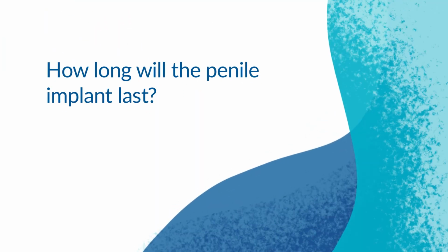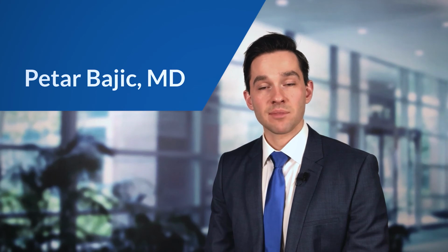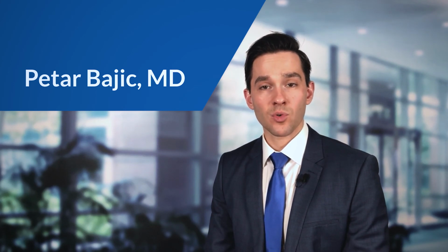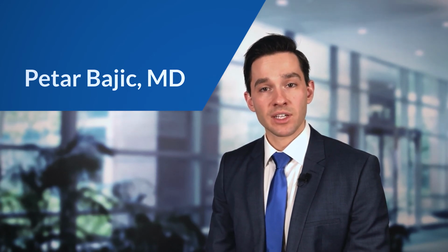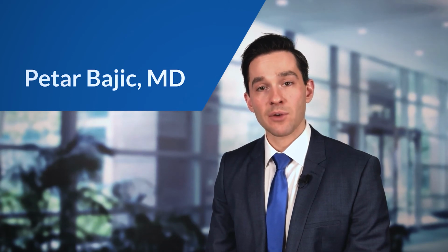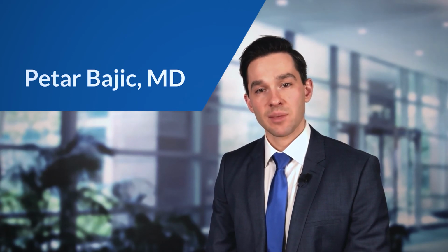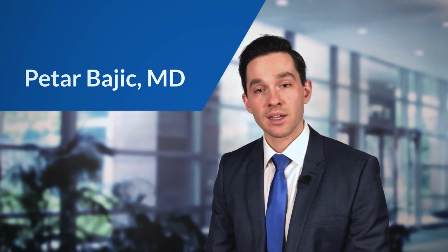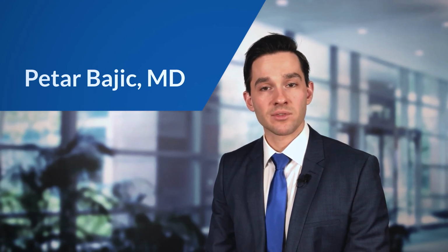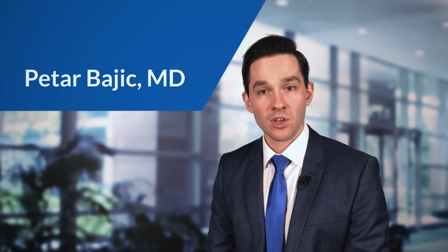As far as how long the penile implant lasts, I've seen many men who've had the device for over 30 years and still use it regularly. However, in general, the risk of having to have the device replaced within 10 years is about 15%. This typically happens because the tubing that connects the components might crack and allow some of the internal salt water to escape. You may notice that the device doesn't get as hard as it used to, or that the device will not inflate at all. This is a reason to replace the device.